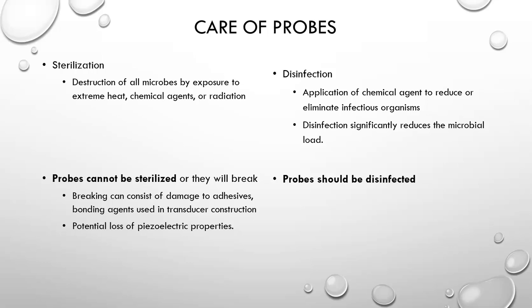Taking care of our probes is very important and has become so important that it is now part of the ARDMS exam. You have to know that you cannot sterilize ultrasound probes directly. Sterilization is the destruction of all microbes and their spores by exposure to extreme heat, chemical agents, or radiation. If you expose an ultrasound probe to those kinds of conditions, you will destroy the probe. What we utilize in ultrasound is disinfection.